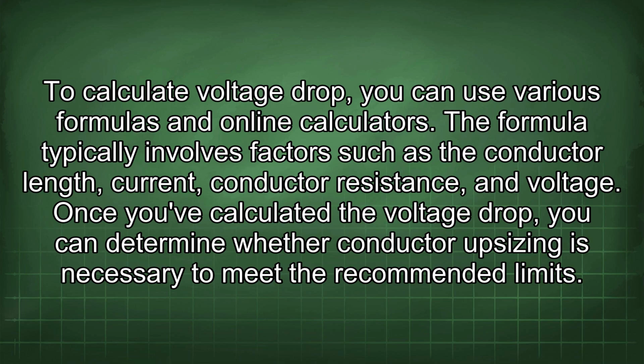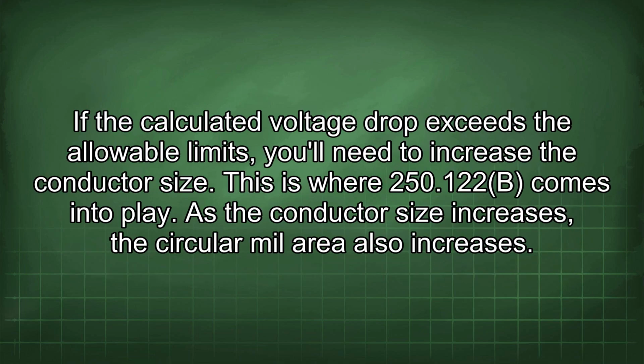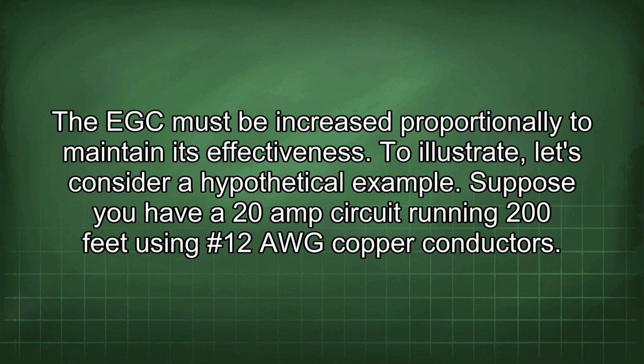Once you've calculated the voltage drop, you can determine whether conductor upsizing is necessary to meet the recommended limits. If the calculated voltage drop exceeds the allowable limits, you'll need to increase the conductor size. This is where 250.122(B) comes into play. As the conductor size increases, the circular mil area also increases. The EGC must be increased proportionally to maintain its effectiveness.